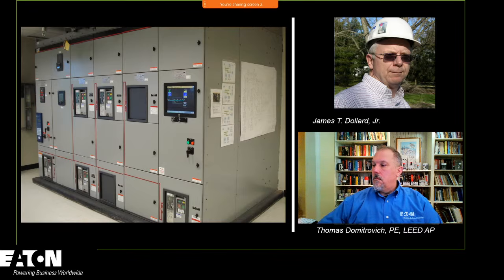There's a second informational note that tells you where to go for that information. It tells you to go to Table 130.5(C) for examples that increase the likelihood of an arc flash incident. So the committee gives you those examples. One of the best examples would be racking a circuit breaker into switchgear or racking out a circuit breaker. We are interacting with the equipment in a way that increases the likelihood of an arc flash incident.